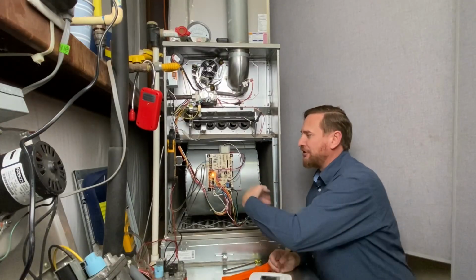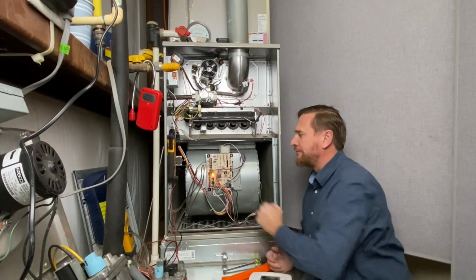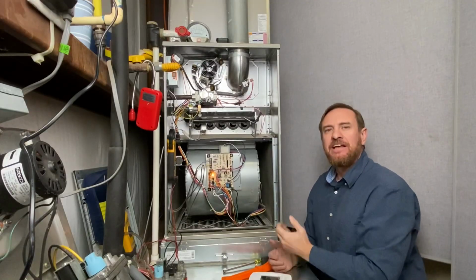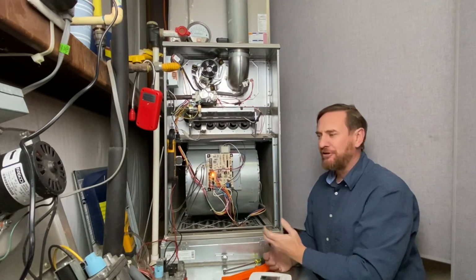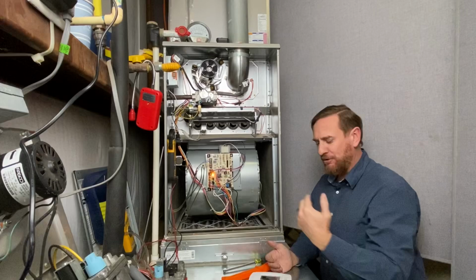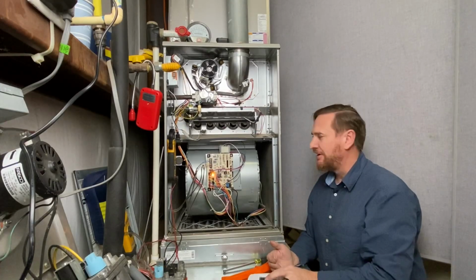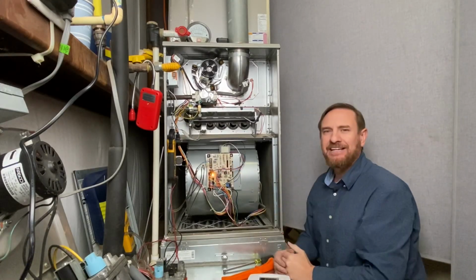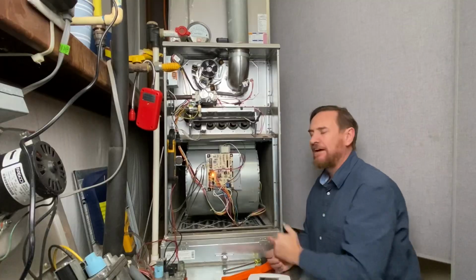So we want to make sure the thermostat's calling for heat, that we're getting 24 volts all the way back to the IFC. If you're in an attic on a 2-story house or on the roof of a commercial building, you may not want to walk all the way back to the thermostat to turn it on. You can simply use a jumper wire and connect R to W and have that call for heat.